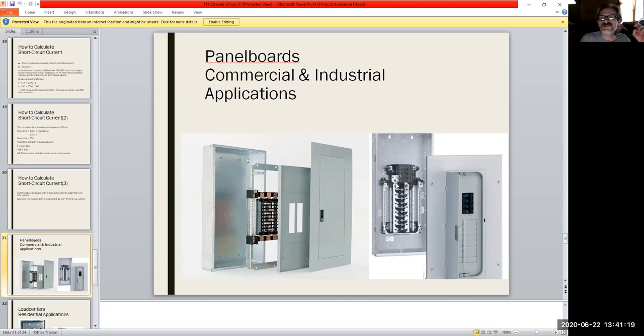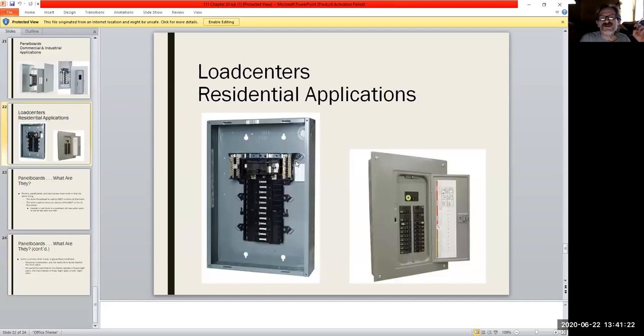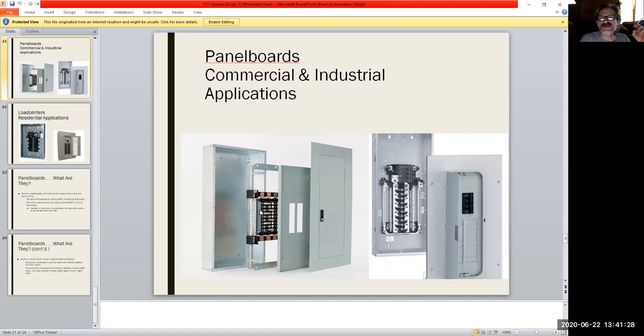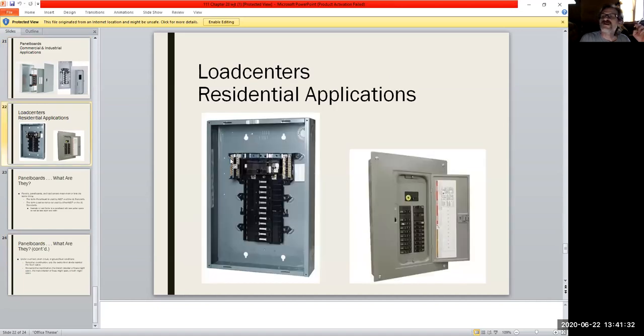You could see in this case, we have two different branches, right? Two hots coming in. And you notice it's very similar to this, except this one has three hots coming in. So in ours, we have two 120 lines coming into it with one neutral bar. So we would make two branches down this way. Circuit breakers would go here and circuit breakers would go here. So you end up populating something a lot like this. And there's your main disconnect, and these are your branches. These are the two hot sides here, a 120 on this side and a 120 on this side. You can tell those are your two pole breakers and your single pole breakers, all fed through, with labeling for each one.